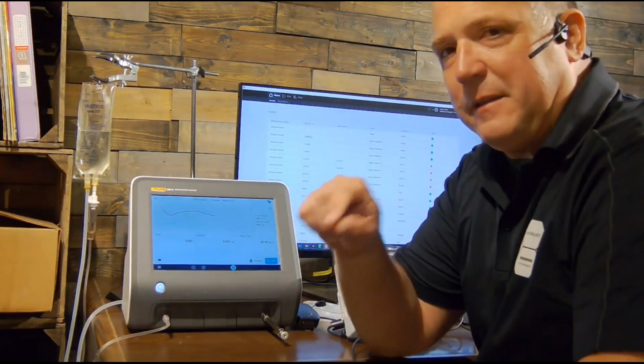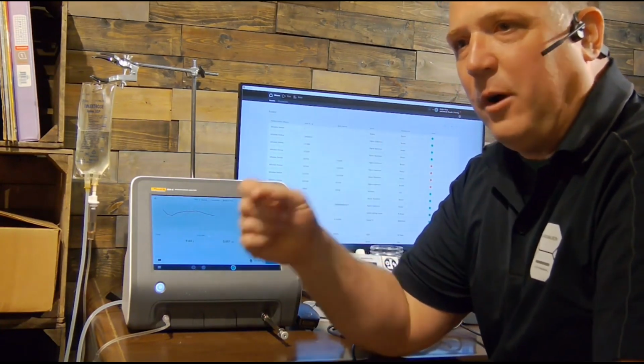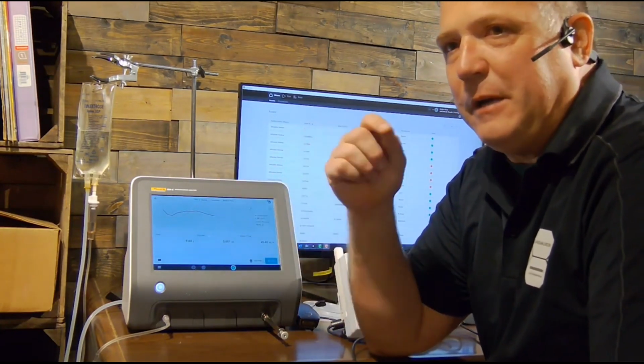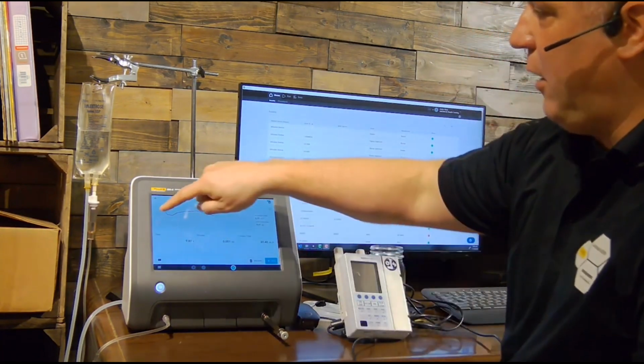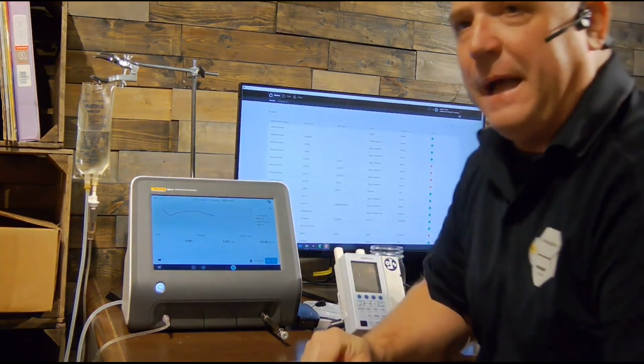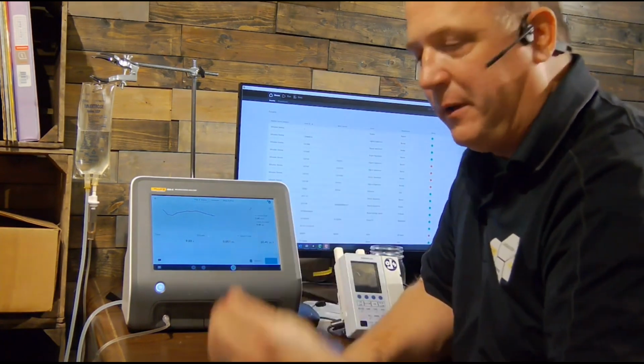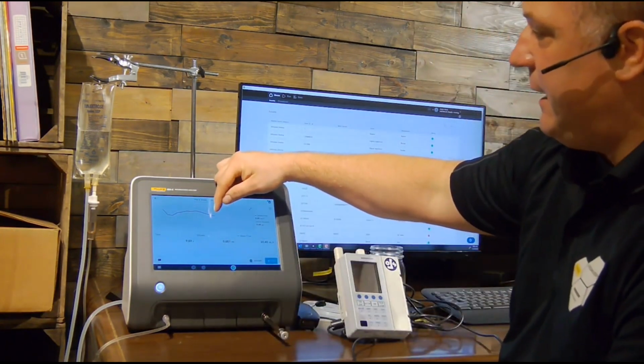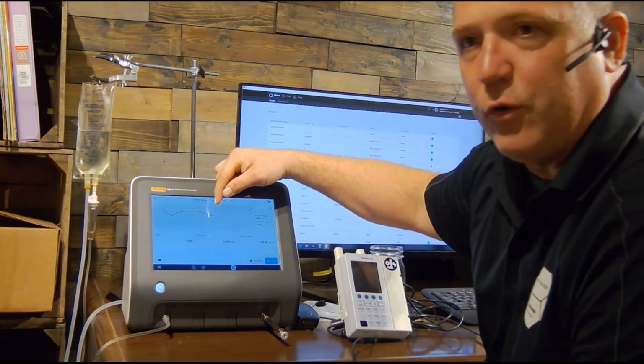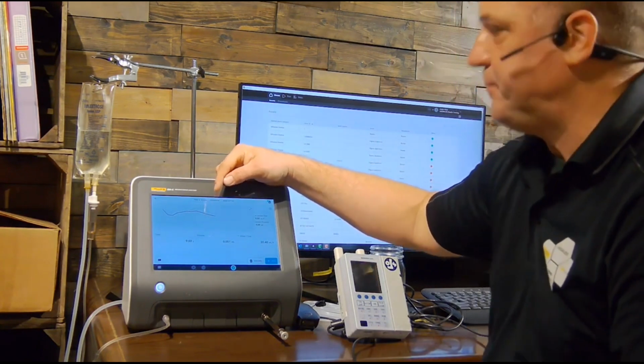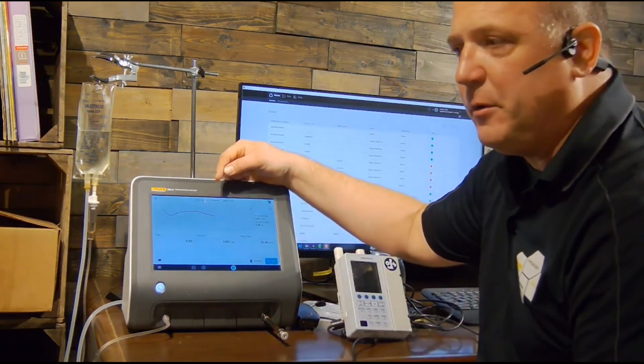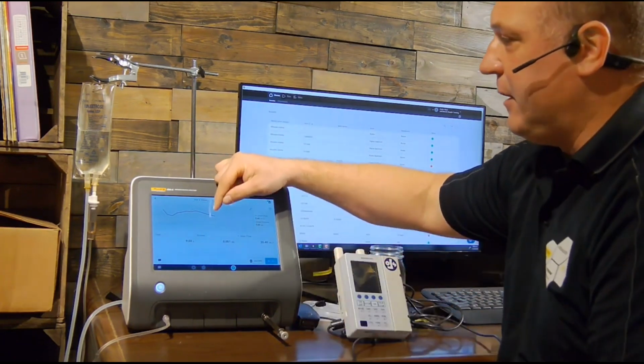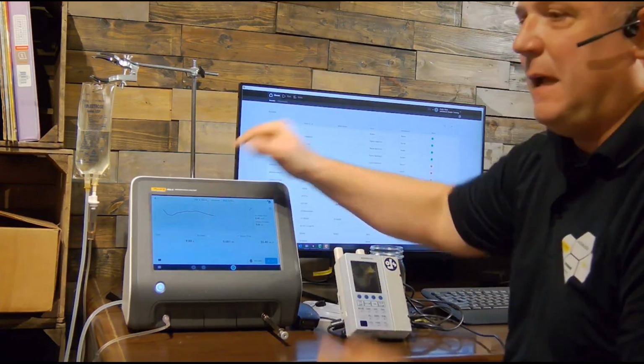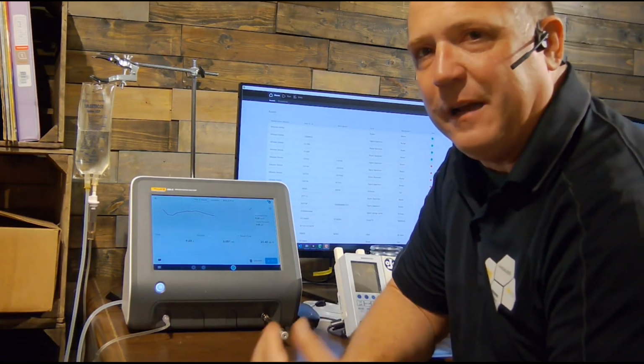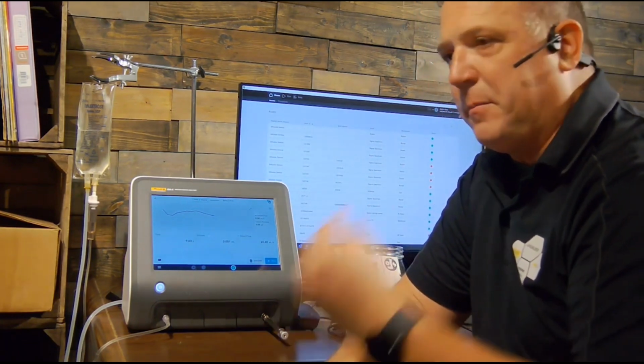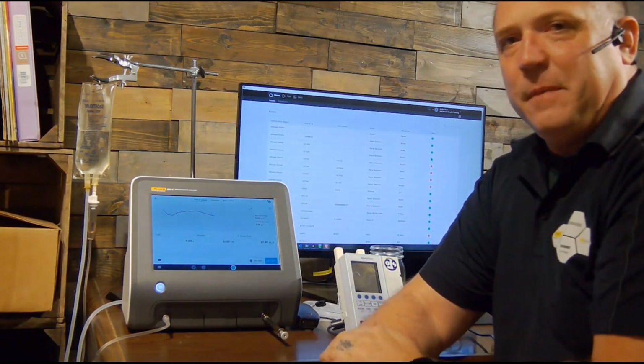Now, what I want to tell you about that is the IDA-6 is so smart that it knows it takes exactly 3 microliters to start a test. So it'll measure the average flow, then go back in time 3 microliters and make that the start point. And at the end of the test, once it sees more than a 50% drop in flow, it knows the test is probably ended. If it doesn't see the volume go above that 50% mark again, it's going to mark that as the end of the test. Because of this, the resolution of the IDA-6 is better than 1% for most of our tests. And that's just amazing technology.